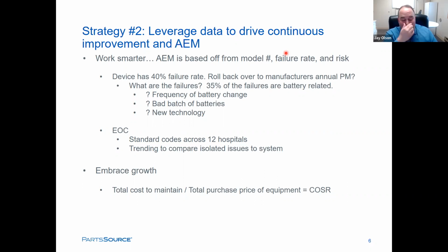There was a dark cloud—I don't know if anybody can recall that, but 8 years ago, I swear there were batteries failing all over the biomed world. I don't know if whoever creates the chemicals or the lead, or however that works, but there was a bad batch of batteries out there. The other thing is maybe invest in new technology—if the lead acid batteries are failing, go to a newer style of equipment with newer style batteries. It'll last longer. It's another justification for capital.